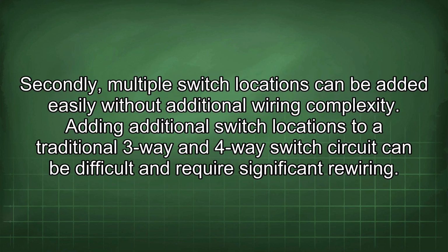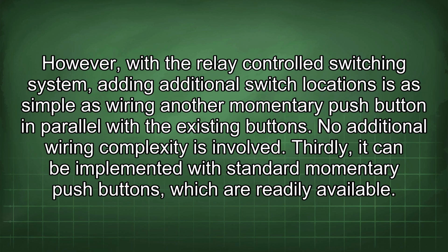Secondly, multiple switch locations can be added easily without additional wiring complexity. Adding additional switch locations to a traditional 3-way and 4-way switch circuit can be difficult and require significant rewiring. However, with the relay-controlled switching system, adding additional switch locations is as simple as wiring another momentary push button in parallel with the existing buttons. No additional wiring complexity is involved.